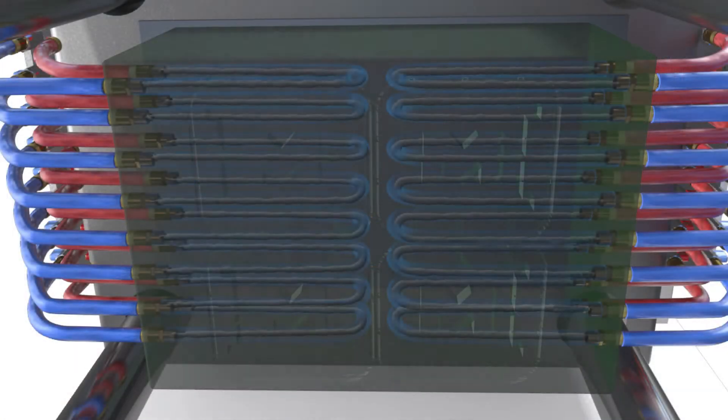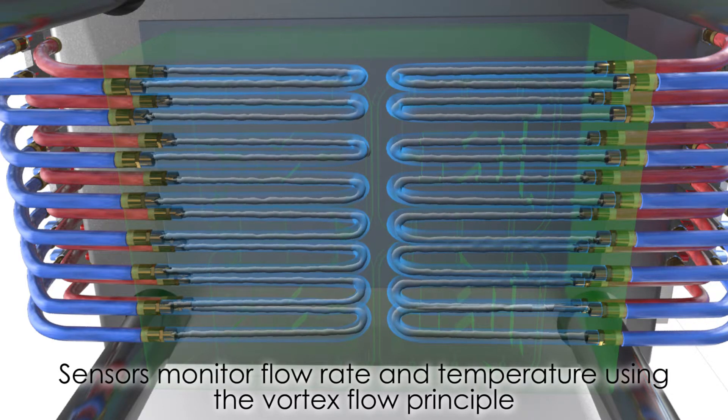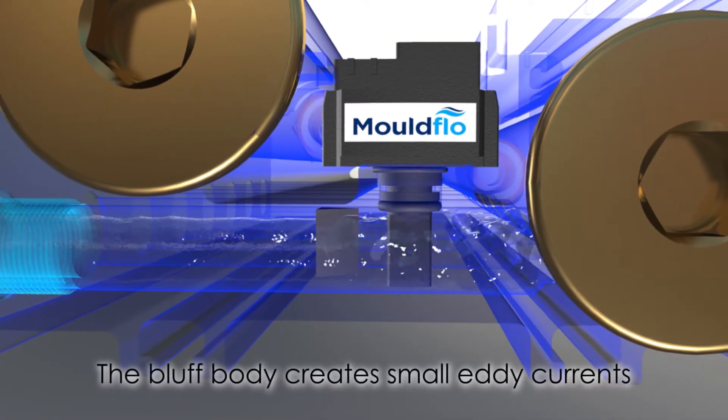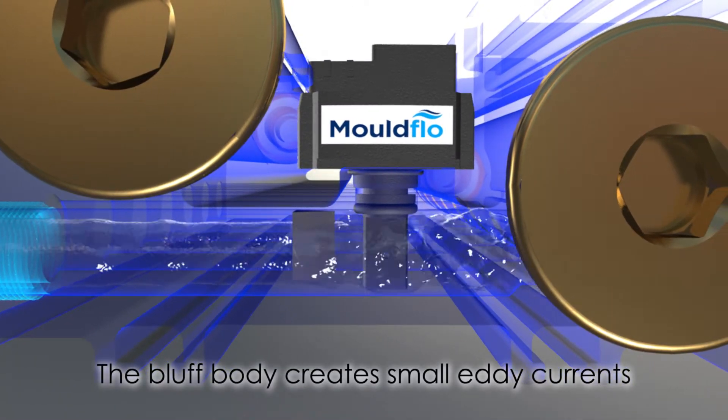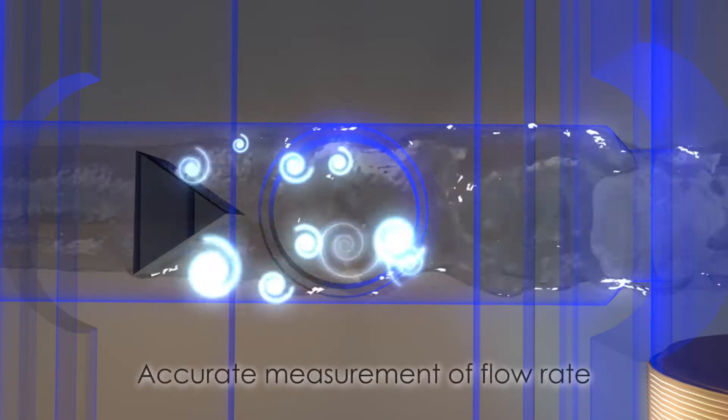As the water flows through the system, the sensors continually monitor flow rate and temperature. The compact sensor uses the vortex flow principle. The bluff body creates small eddy currents, and by measuring the pressure within these vortices, we can accurately measure the flow rate.